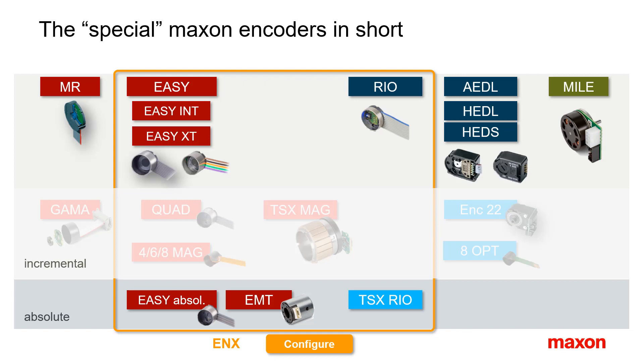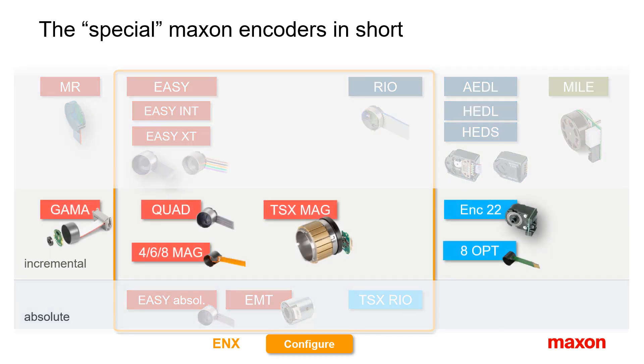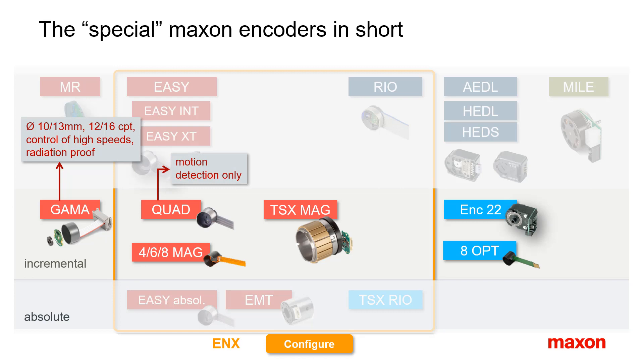After learning more on the main Maxon encoder families, let us have a short look at the specials. The GAMA is a low-resolution magnetic encoder for brushed motors — a magnetoresistive encoder that is insensitive to radiation and can be used in applications with exposure to X-ray or other ionizing radiation. The QUAD encoder gives just 4 states per turn and is rather a sensor for supervising purposes: does the motor rotate and in which direction? It should not be used for feedback and does not work with Maxon controllers.